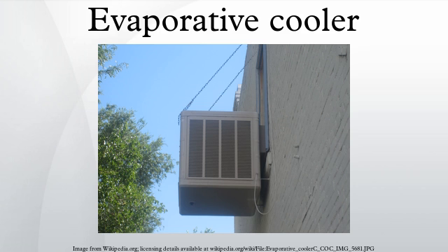As an example, in Las Vegas, Nevada, with a typical summer design day of 108°F dry bulb, 66°F wet bulb, or about 8% relative humidity, the leaving air temperature of a residential cooler would be TLA = 108°F − 85% × (108°F − 66°F), TLA equals 72.3°F. However, either of two methods can be used to estimate performance.